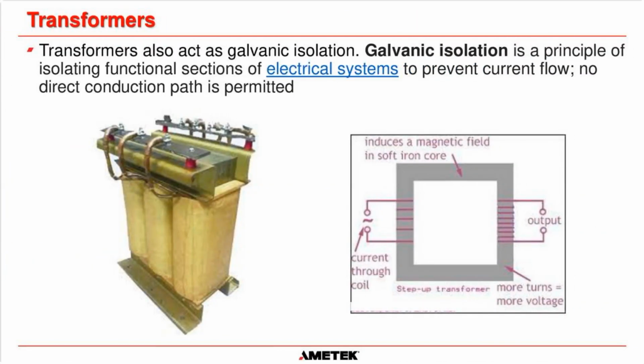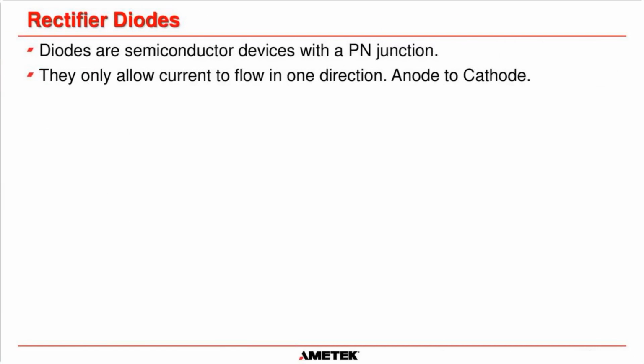The other thing our transformer does, because it's an isolation transformer, is act as galvanic isolation. It's the principle of isolating functional sections of an electrical system to prevent current flow - meaning there's no direct connection between the primary wires and the secondary wires. They are just wound round the core, and the magnetic flux in the core induces a current on the output winding when you have a fluctuating current on the input winding. There is actually no electrical connection between those two wires whatsoever, so we can say they are isolated from each other. And that gives us many, many advantages.